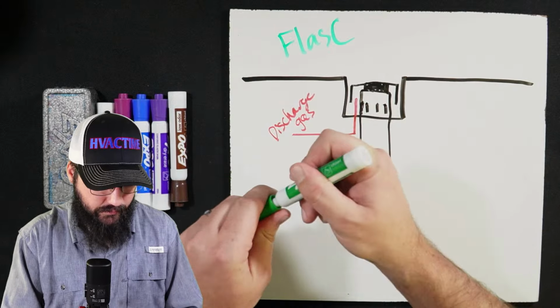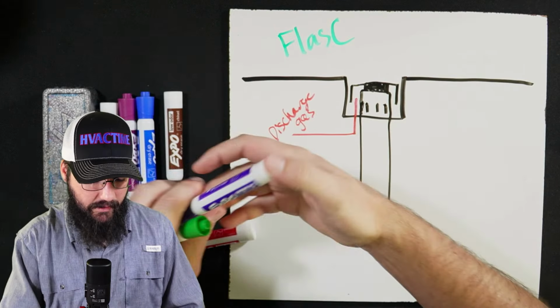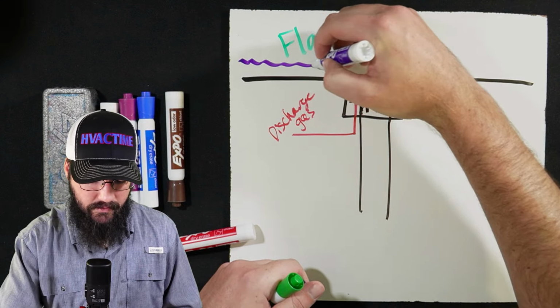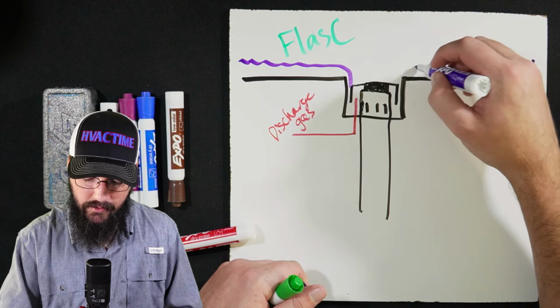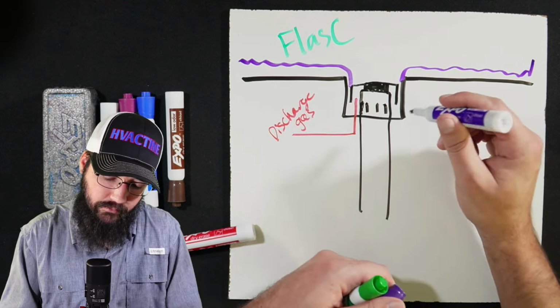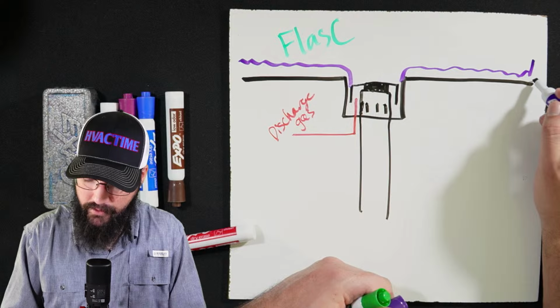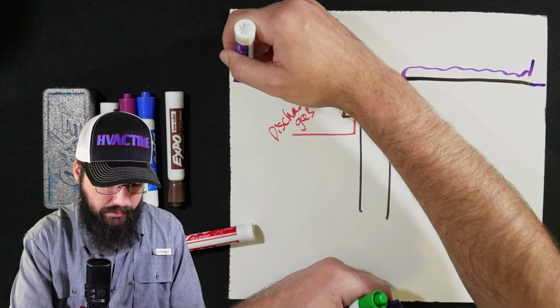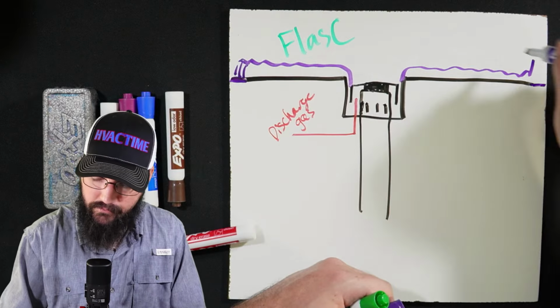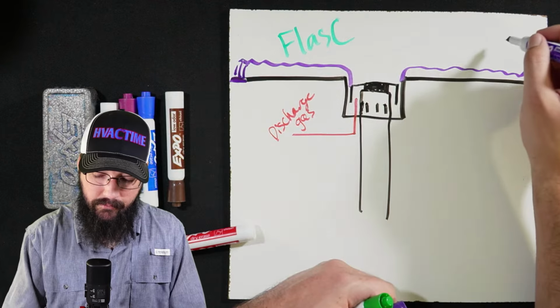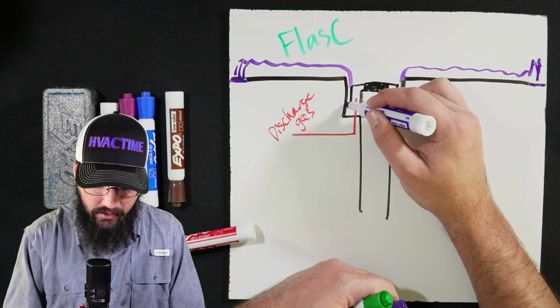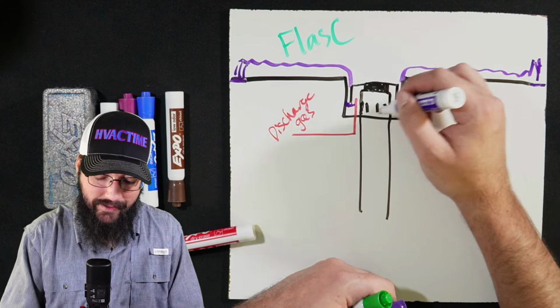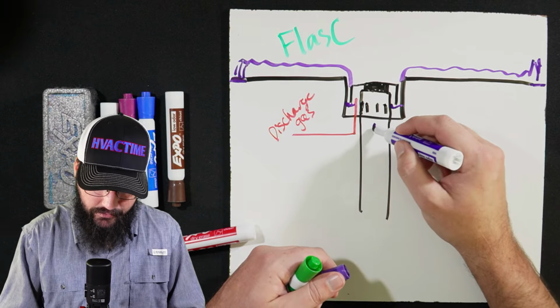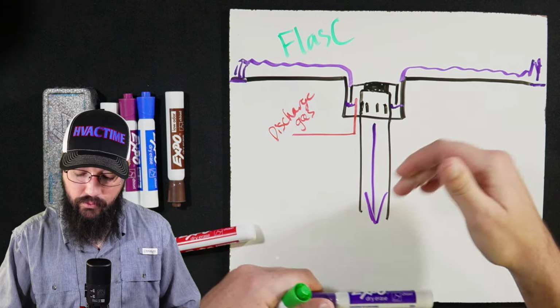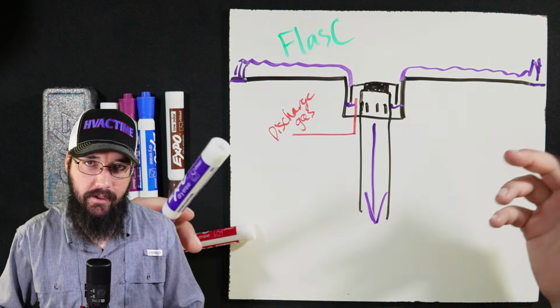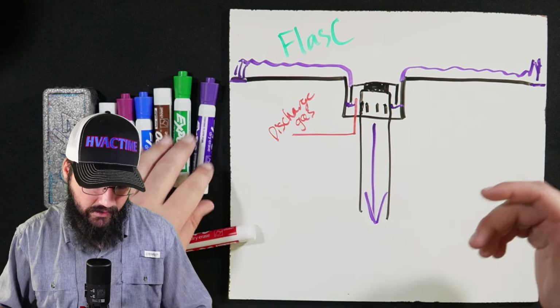And we've got liquid refrigerant that is draining into our float valve chamber itself. And we've got our fixed orifice plates over here metering that liquid refrigerant coming in, and then the vapors rise to the top, and we've got a column of liquid refrigerant collecting in the bottom of this chamber as it then gets metered and flows out to either the economizer or the evaporator. Just kind of depends on the style of machine.